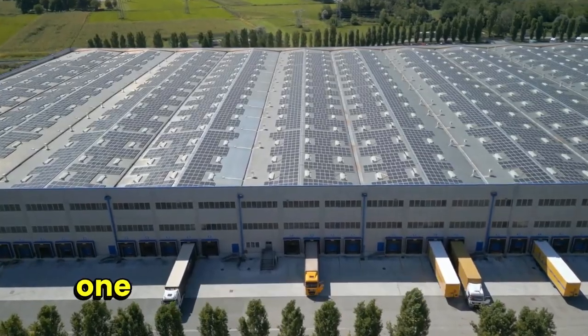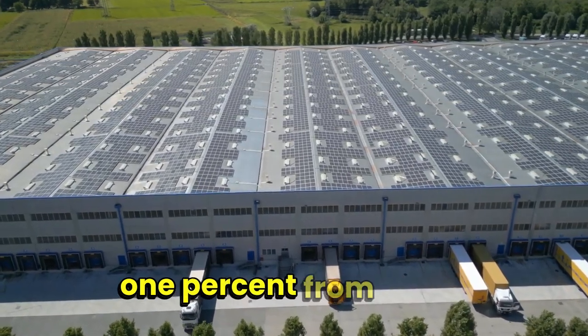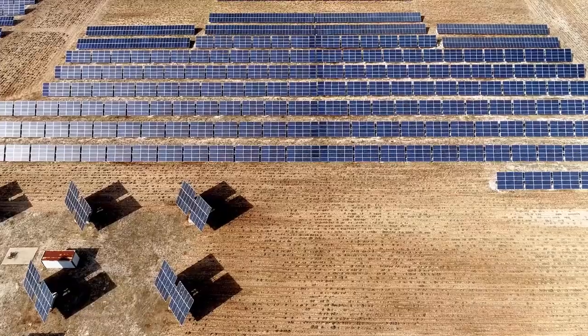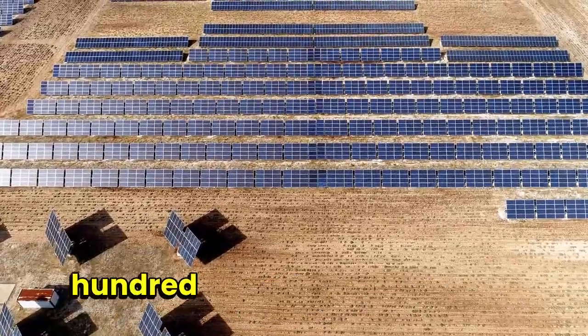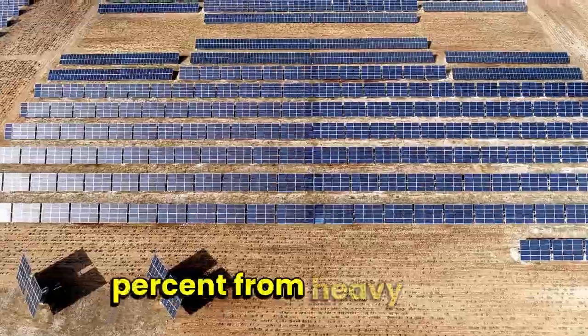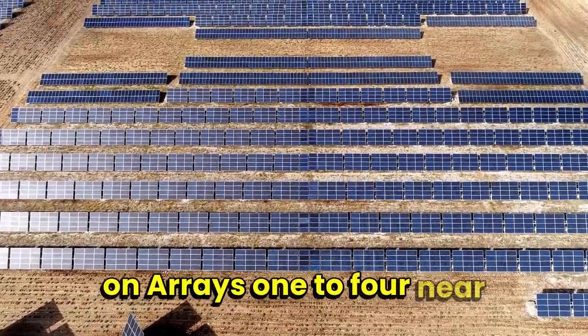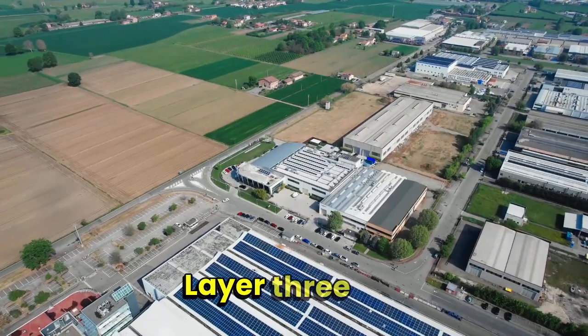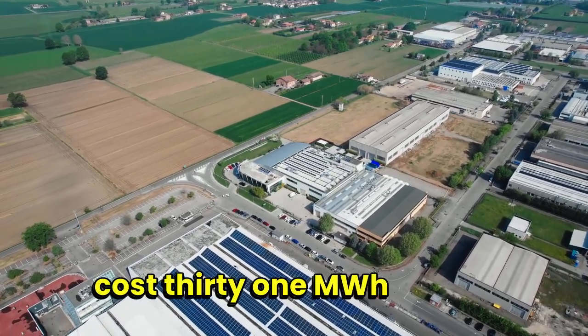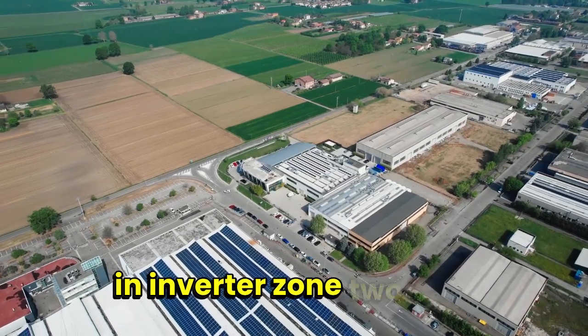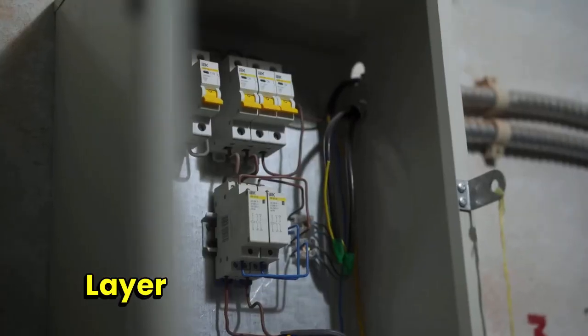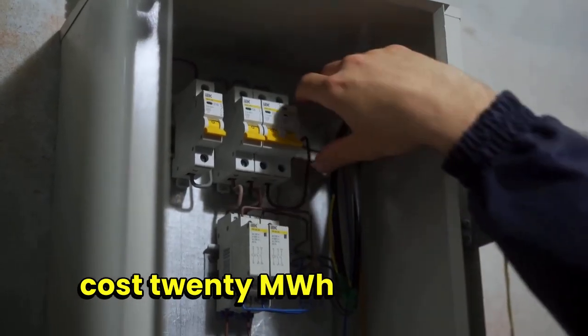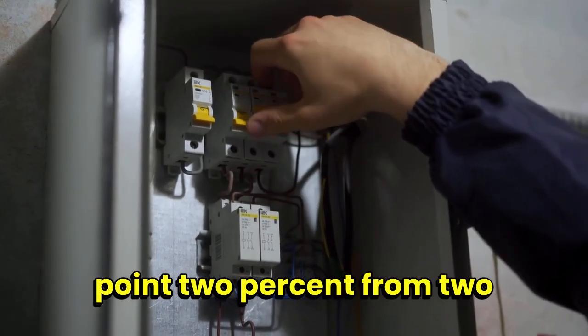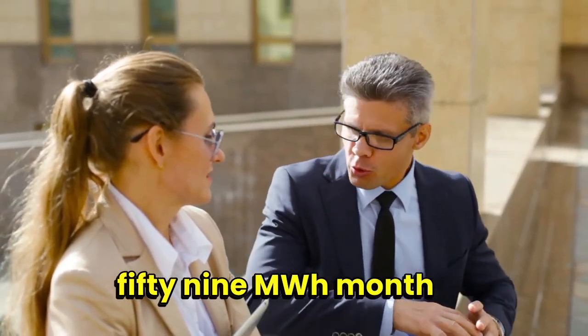Layer 1 shading cost 102 MWh per month, 1% from a new warehouse built 200 meters north. Layer 2 soiling cost 306 MWh per month, 3% from heavy dust on arrays 1 to 4 near dirt road construction. Layer 3 PID cost 31 MWh per month, 0.3% in inverter zone 2 with a humid microclimate. Layer 4 equipment issues cost 20 MWh per month, 0.2% from 2 underperforming inverters. Total 459 MWh per month, or 4.5% fully explained.